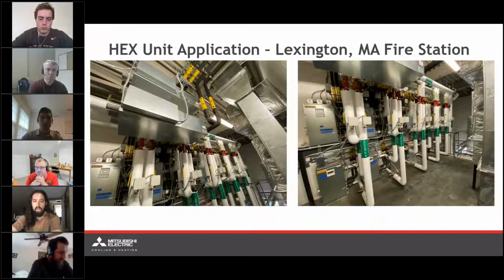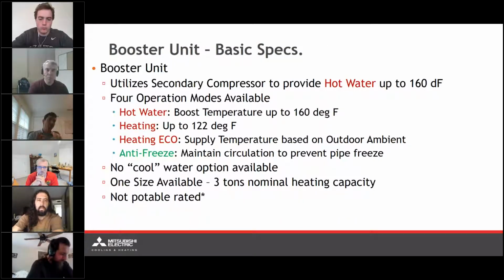Okay, so I'm just going to move forward. Separate from the aux units, those are units with heating and cooling capability, we also have our HEX booster unit. Now, the booster unit is similar to the aux unit, still acting as a heat exchange device between the VRF's R410A refrigerant loop and a water loop. However, the booster unit also contains a secondary R134A refrigerant loop within itself, with a secondary compressor that allows the unit to produce even warmer water. So in this particular unit, you have a hot water mode in addition to the heating mode, which boosts the water temperatures up to 160 degrees.